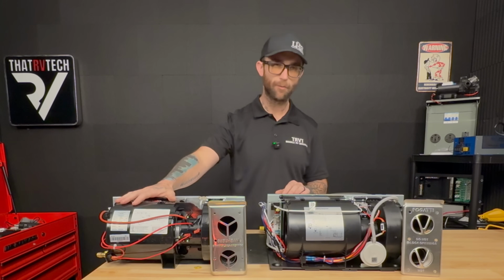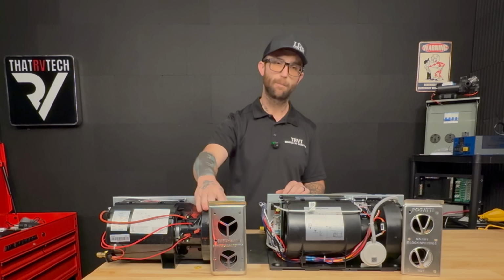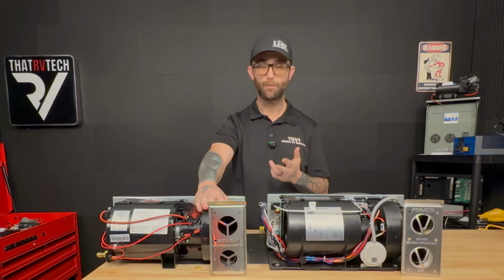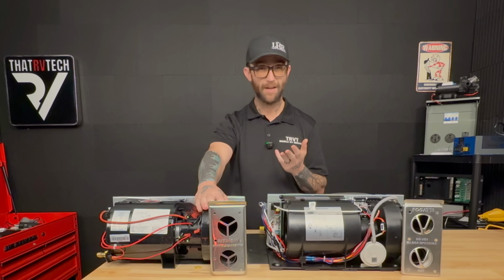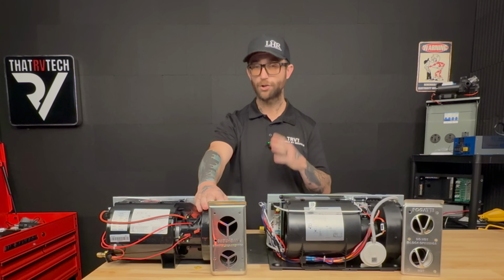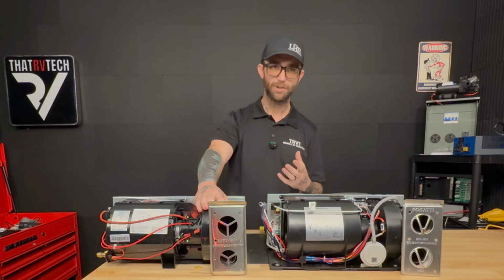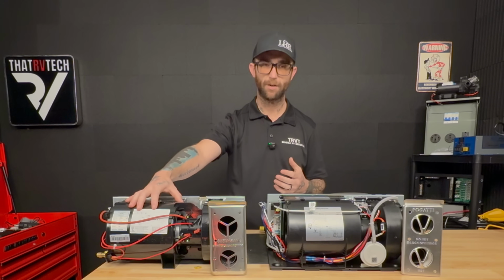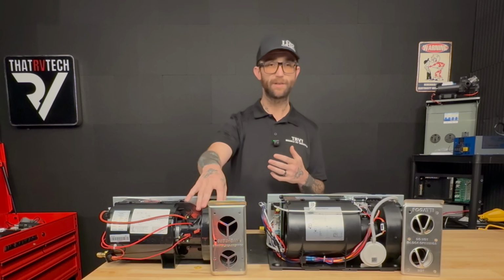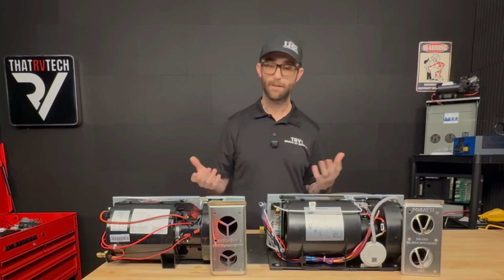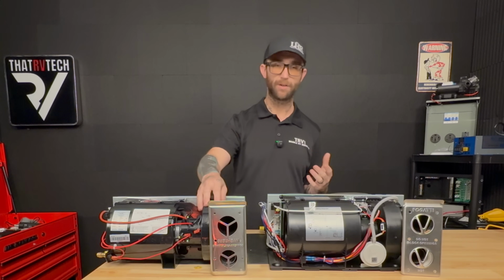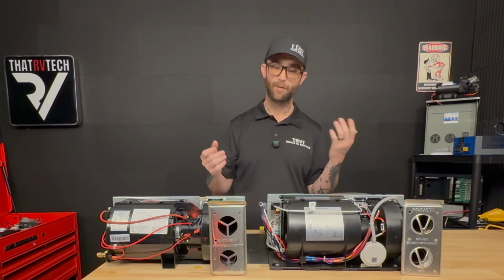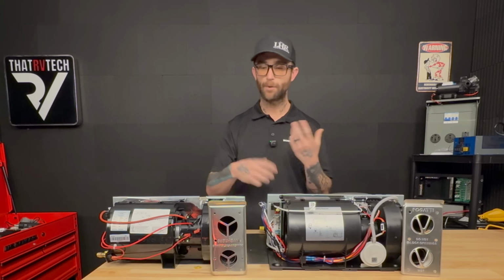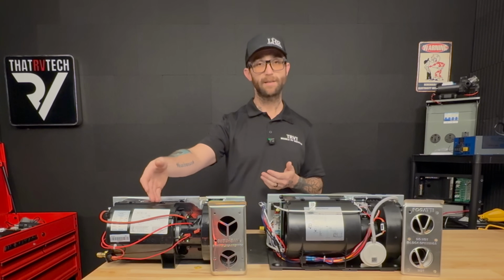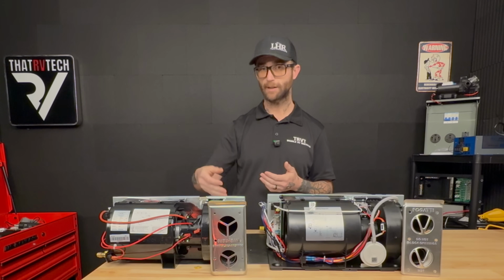Just because we have airflow over here does not mean that the combustion wheel hasn't melted, hasn't come loose from the shaft, that it hasn't shredded itself. There's no way to confirm that there's airflow in the combustion chamber simply by checking it over here. Do both fan wheels use the same motor? Yes. But I've run into plenty of situations where you've had melted fan wheels that have come off. You know, they're broken, they're not producing airflow. But hey, this side is spinning, so it's going to tell this furnace to keep burning.